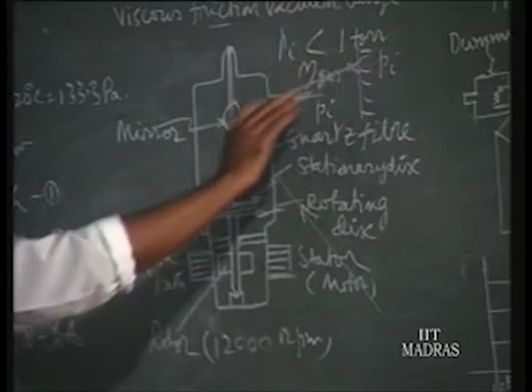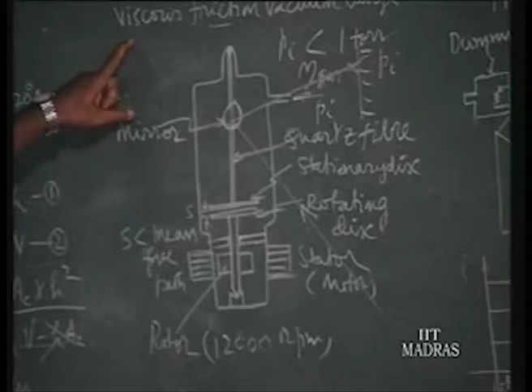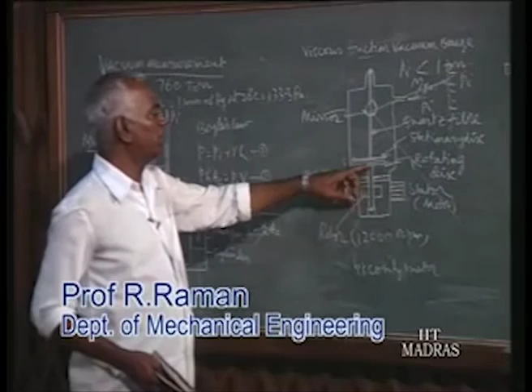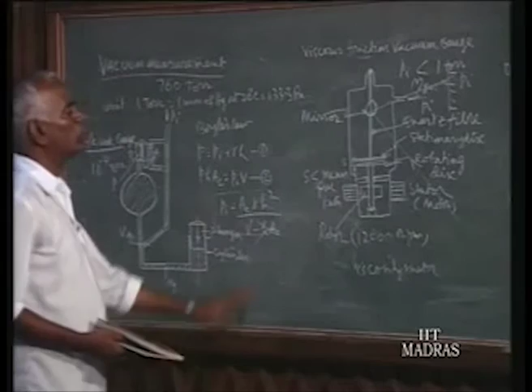Also this instrument is used in finding this principle, that the viscosity is proportional to pressure. The torque transmitted to the disc is proportional to viscosity. That principle is used in the viscosity meter also. For measuring viscosity of liquids, you find a similar arrangement. The rotating disc is there, and the liquid at different temperatures will be kept there. Whatever torque is transmitted is proportional to viscosity. That is the same principle used there, but here we are using that principle for vacuum measurement.